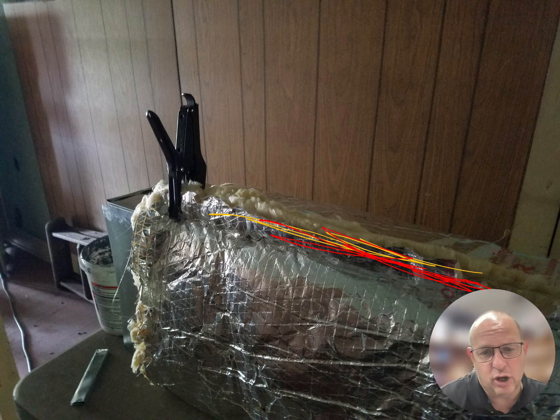A lot of people will just use tape on this fiberglass insulation. That is the wrong way to install fiberglass insulation. Fiberglass insulation needs to be stapled, and after you're done stapling it, that is when you tape it. Now, this is a foil back insulation, which you'll be using out in the field. This is a vapor barrier insulation that's going to keep the moisture from entering into the insulation and getting close to that ductwork and then sweating on that ductwork. So it's very important that if you get any scrapes, any gashes, any holes within that foil, you use the foil tape that comes with this ductwork insulation.